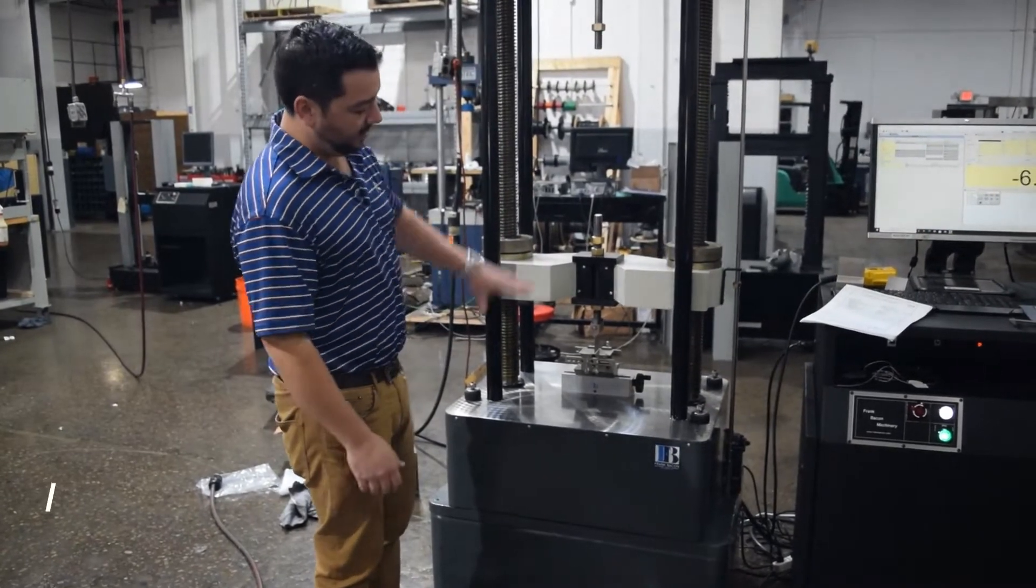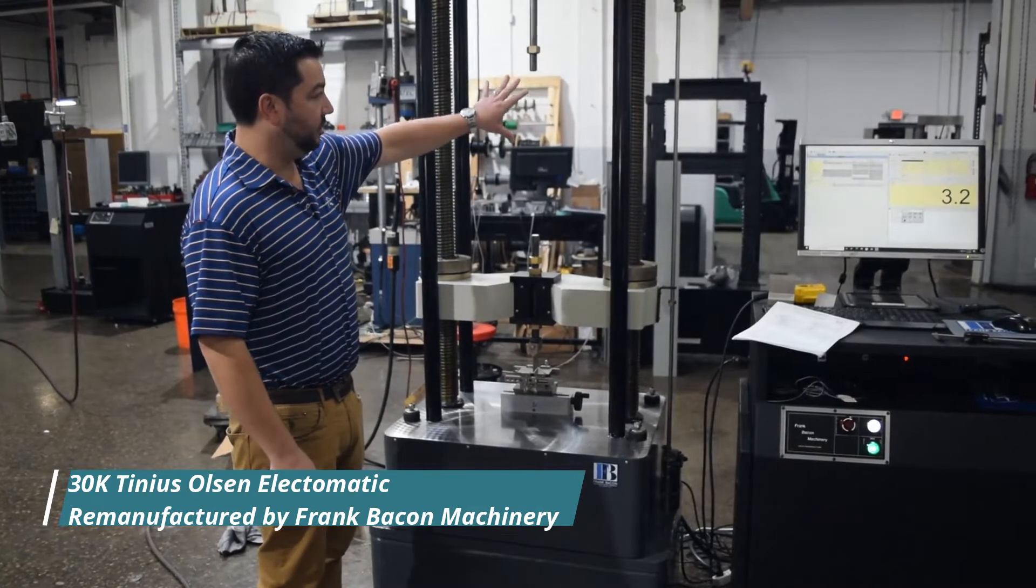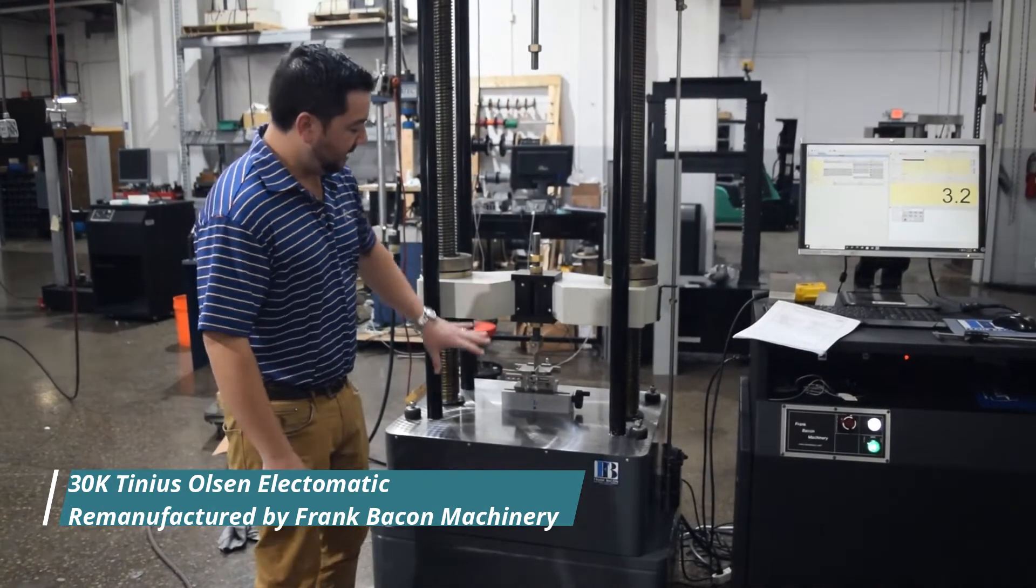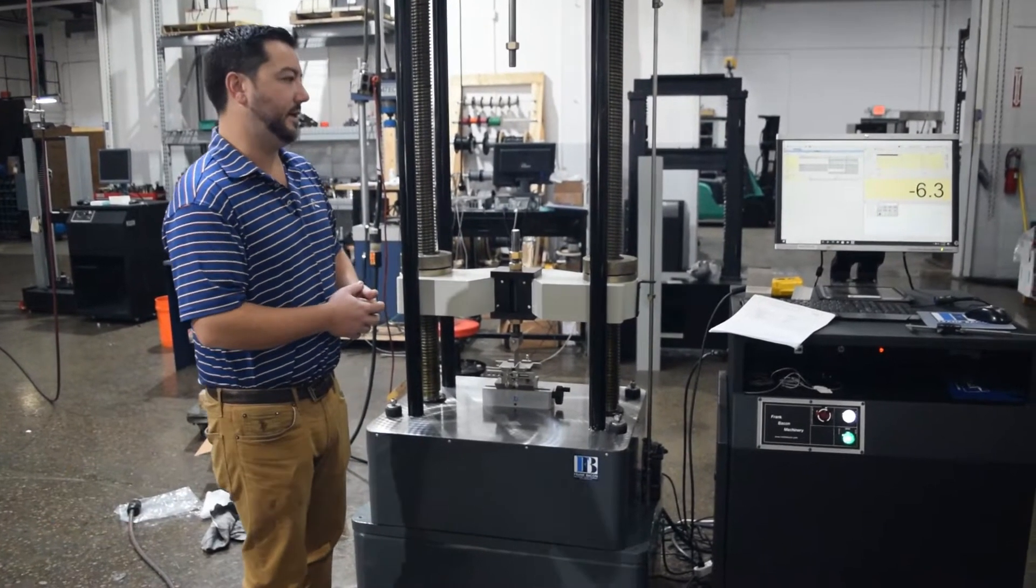Today we have the 30K Electromatic, which is a dual space machine. Customers are able to do tensile testing on the top and bend testing on the bottom without having to remove or change fixtures at any time. It works out really well for them.